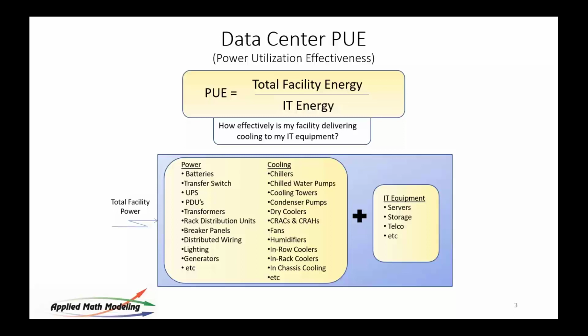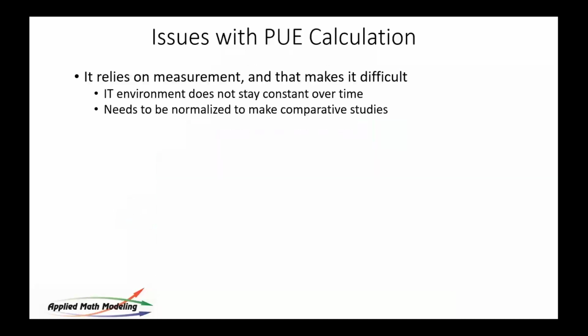But this particular metric has come under some criticism lately, and we think rightly so. Both Henry and I agree on this. PUE has some issues. For one, it's very difficult to measure. That is, the IT load itself doesn't stay constant. So trying to figure out what your IT load is difficult. You have to do this, by the way, for a whole year. PUE should be an annual number, not an instantaneous number.